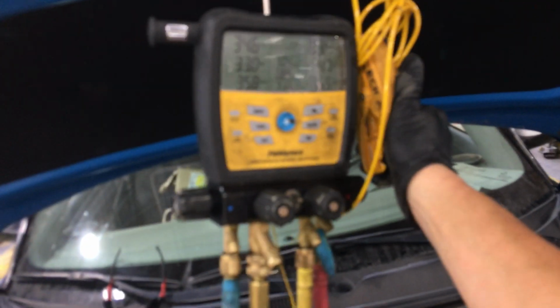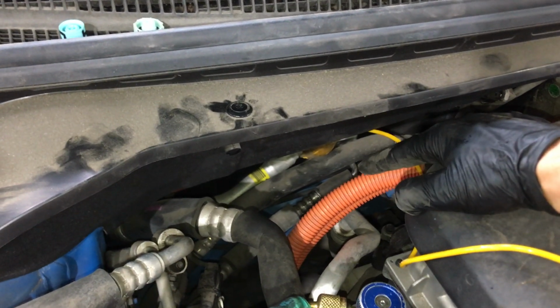That's the evaporator, and the liquid line going in is colder. Let me see if I can get a temperature sensor on that. I can't get my big clamp on it, I need my little needle one. I think I'll make another video because I can't get one of these clamps on there. It has to be the little duck-billed clamp to get on that tiny line. You see that little silver line? That's supposed to be the warm liquid feeding the expansion valve inside, and it's colder than the suction line coming out.